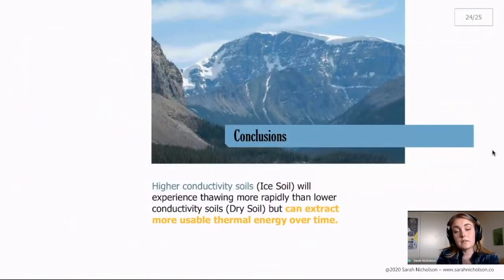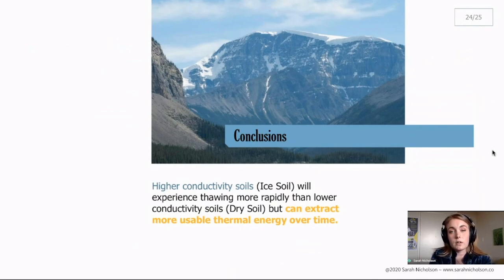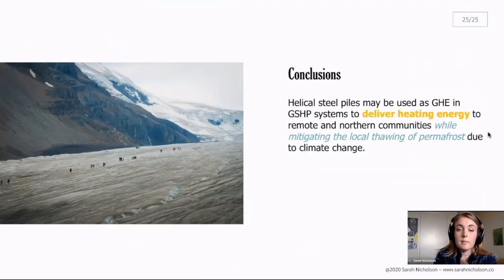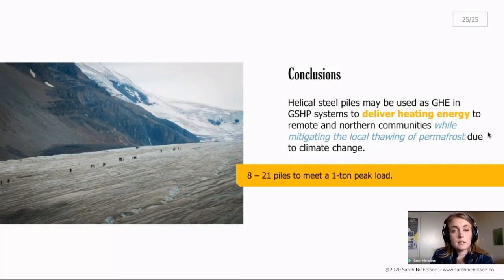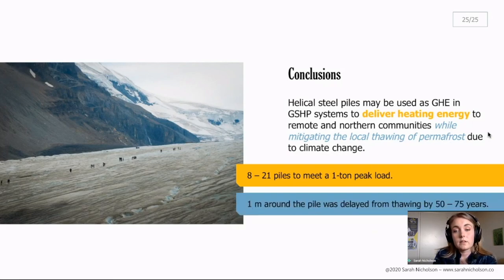So in conclusion, the conductivity of the soil had a significant effect on its response to warming. Where the higher conductivity soil was not as benefited from the ground thermal imbalance, but it was able to extract more usable thermal energy over time. So these ice soils may warm quicker due to climate change, but we can also use them for greater thermal energy production. But for both cases, it was shown through this research that these helical steel piles are usable as the ground heat exchanger in these ground source heat pumps. They are able to deliver heating with only 8 to 21 piles required to meet a 1 ton peak heating load. And also, they can mitigate the local thawing of permafrost in these regions due to climate change. So around 1 meter of the soil was delayed from thawing by 50 to 75 years.